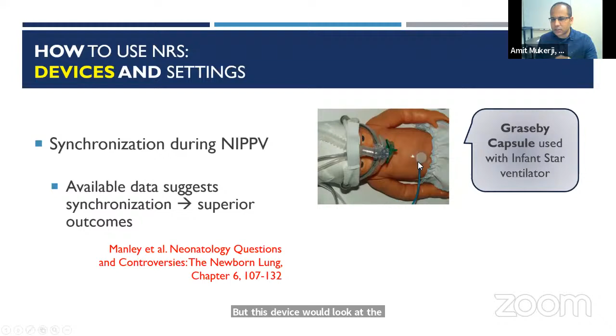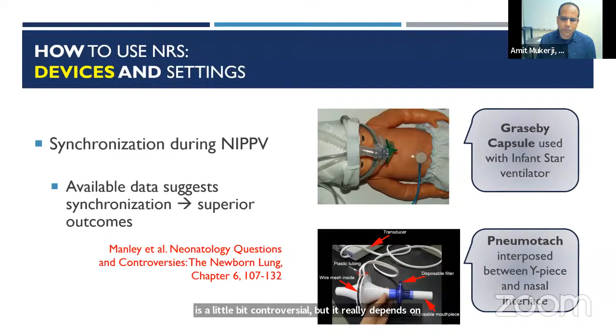The other way to do this is using a pneumotach or some kind of a flow sensor that's interposed between the Y piece and the nasal interface, which would attempt to detect a signal of flow into the baby as the baby is trying to take a breath in and send a signal to the ventilator. How well these work is a little bit controversial, but it really depends on the device type and which kind of pneumotach is being used.